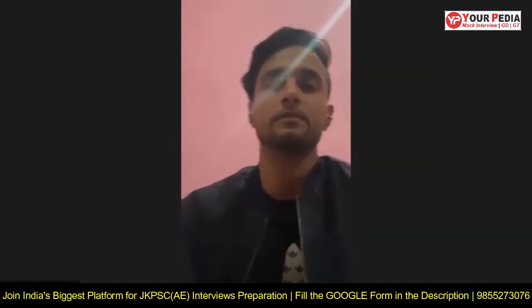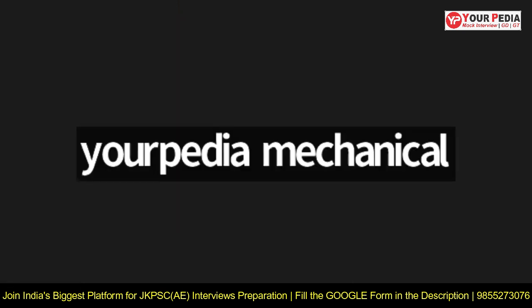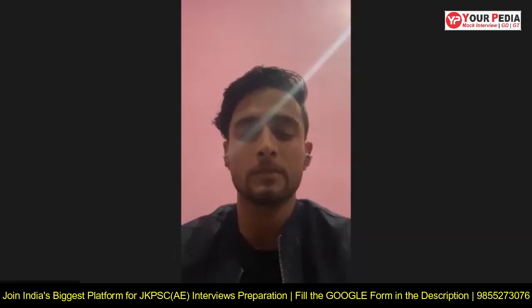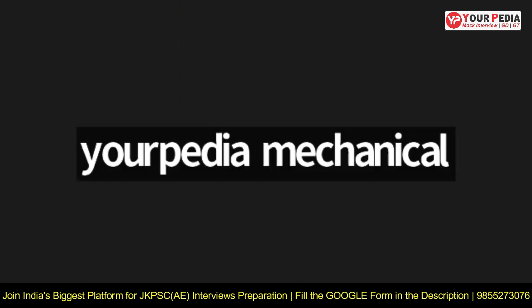So in that case, the cost of those expansion devices will not be justified if you are using some piston cylinder arrangement or turbine. That's why we go with a very simple, cheap expansion device known as the capillary tube. In that capillary tube, there will be no work output. Expansion we carry out by passing the fluid through a very narrow tube.